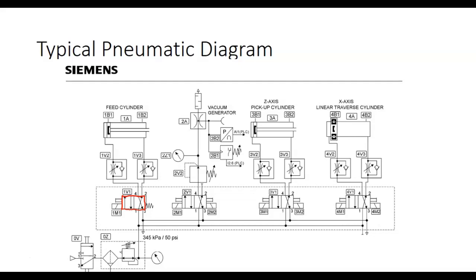So this is a 2-position valve, and it's got 4 ports. Your odd port numbers are your pressure ports, so 1 is your pressure and 3 is your exhaust. Your even numbers are your working ports, the ones that are actually controlled, that get shifted around. The way these symbols are drawn, this would be a 2-position, 4-port valve.